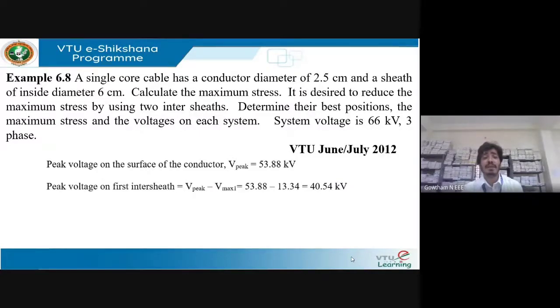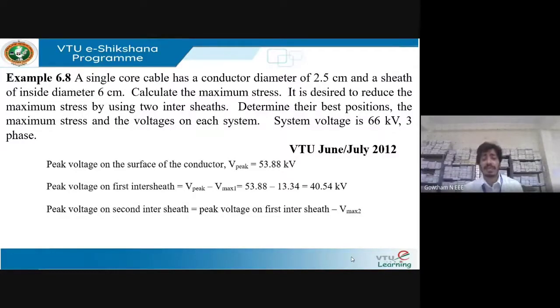The peak voltage on the first intersheath = V_peak − V_max1 = 53.88 − 13.34 = 40.54 kV. The peak voltage on the second intersheath = peak voltage on first intersheath − V_max2 = 40.54 − 17.86 = 22.68 kV.